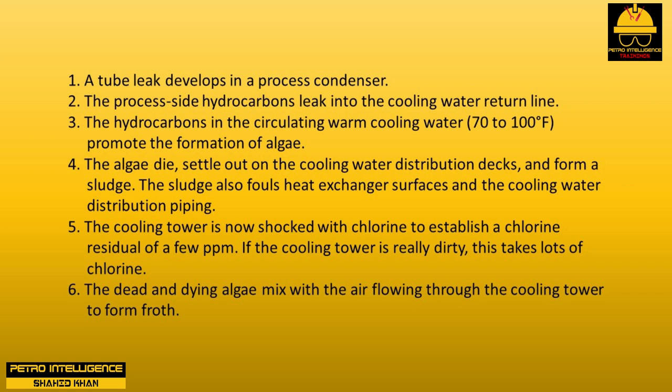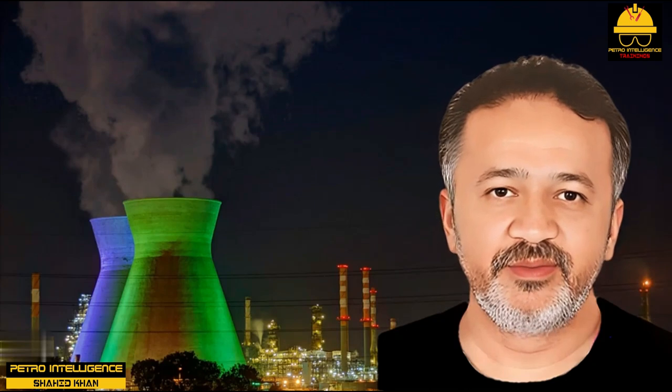The sludge also fouls heat exchanger surfaces and the cooling water distribution piping. Five, the cooling tower is shocked with chlorine to establish a chlorine residual of a few ppm — if the tower is really dirty, this takes lots of chlorine. Six, the dead and dying algae mix with the air flowing through the cooling tower to form froth. To maintain a clean cooling water system requires maintaining a chlorine residual of a few ppm. Organic material leaking into the cooling water consumes chlorine; without a residual chlorine content, an organic sludge will form. The prerequisite for maintaining good heat transfer in cooling water exchangers is to eliminate hydrocarbon leaks into the circulating water system.